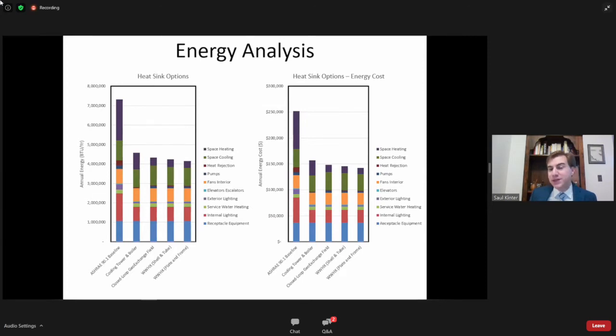It's worth mentioning that this building still has a cooling tower. The heat exchange unit provides 100% of the capacity, so we can run off either the wastewater system or the cooling tower or both. The motivation for the cooling tower, aside from just the resilience benefits of having two systems, was actually to help us reject rainwater. So in DC, one of our problems is we have too much rainwater at times, and we need to do a better job of getting rid of it. So by having the cooling tower there that could reject it more quickly, we were able to reduce the size of our storage cistern, which saved us quite a bit of money elsewhere. The net result was a financial boon to the building, as well as helping us achieve LEED Platinum status.